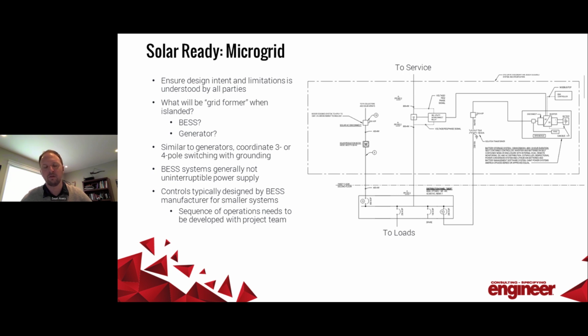Usually in these scenarios, the controls are done by the BESS manufacturer or assembler. When designing these, many times I've mostly just written a sequence of operations and coordinated with at least the basis of design manufacturer to put that system together, but usually the BESS manufacturer is packaging up the system and providing the control system.